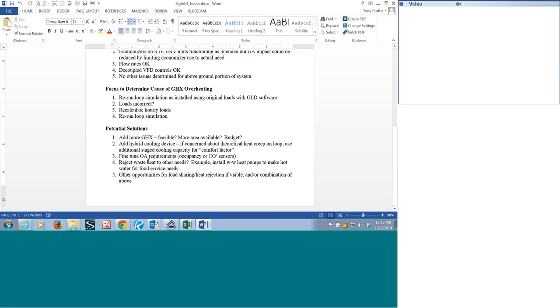We've also been experimenting successfully, I might add, with putting in auxiliary horizontal ground loops, very shallow, and controlling them to run, say, at night, if the surface temperature is too hot during the day. And of course, you have to tailor the controls for this, but what we're finding is a lot of times we can shave heat off with a smaller auxiliary horizontal loop field, maybe even put it in a parking lot, in a parking garage, that sort of thing. It just depends if it's viable. You have to understand your climate, heat gain on whatever surface component. So there's a lot of things to consider, but it is something to keep in mind if the situation fits.